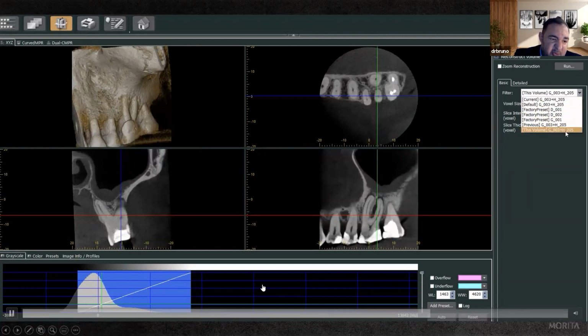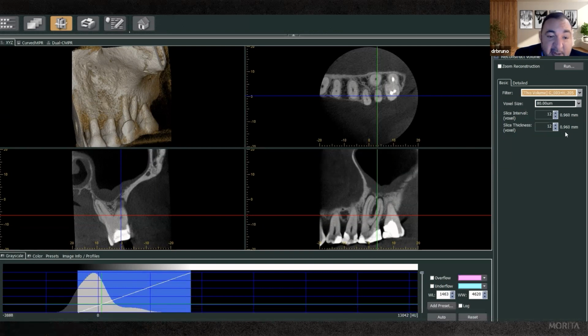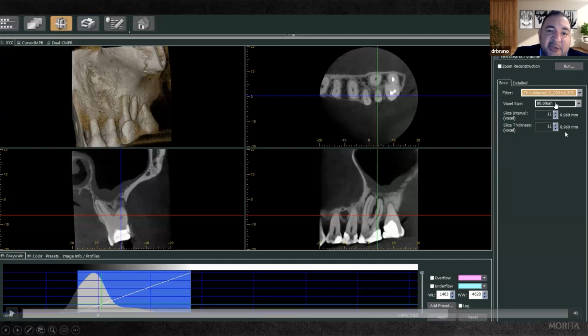One of the things that I want to make sure of is that the unit you guys are using, this particular one here, is the G003 plus H205. Okay, if you're interested in Hounsfield units, if you want to measure Hounsfield units with your Conebeam-CT scan, that H has to be there. You have to be using a plus H filter. If you don't have the plus H filter, you cannot measure Hounsfield units with i-Dixel. Okay, but if you have that, please use it. So ideally speaking, you don't want to change this much.